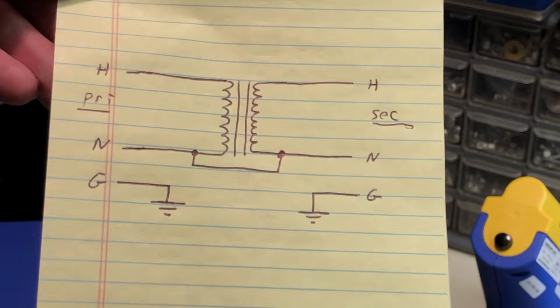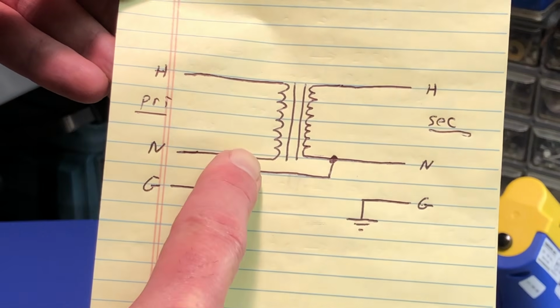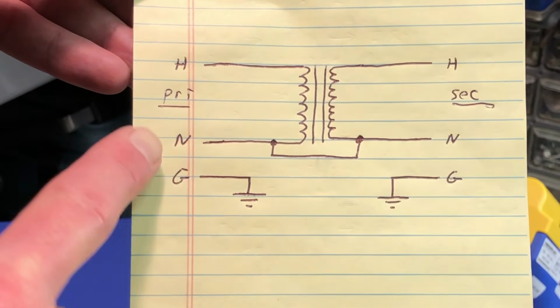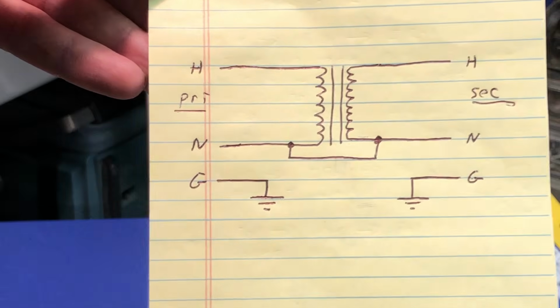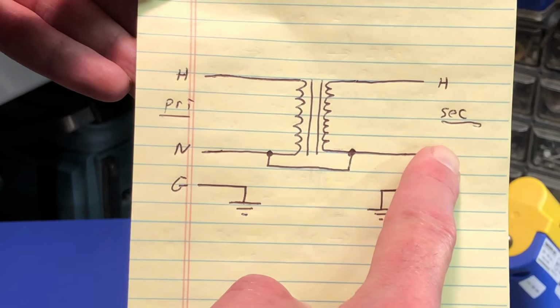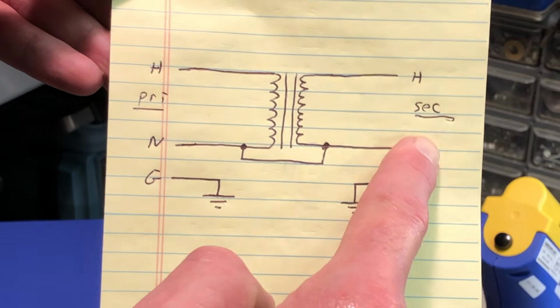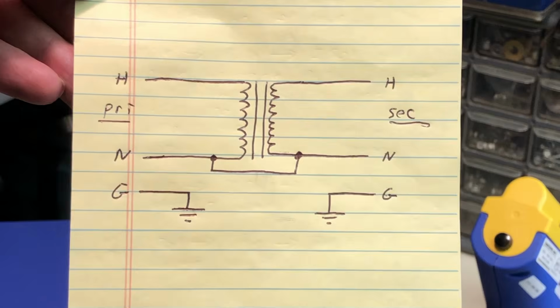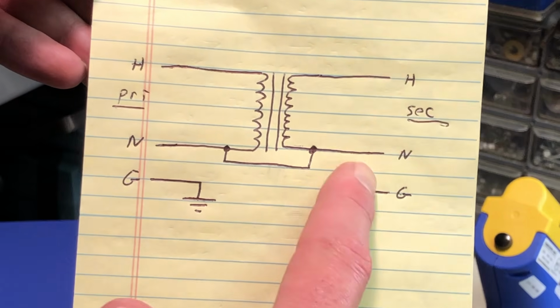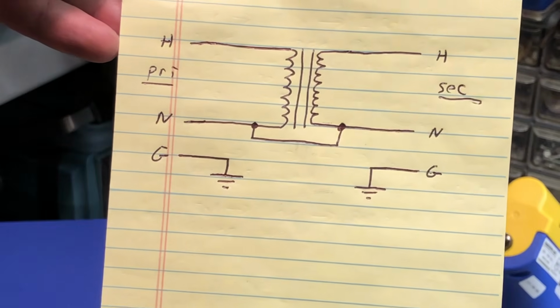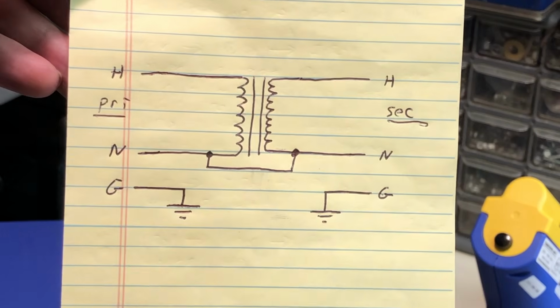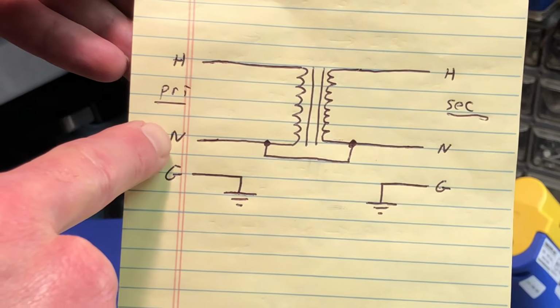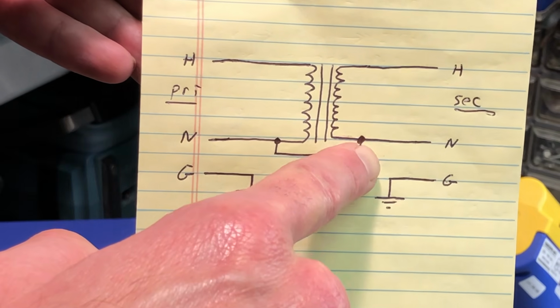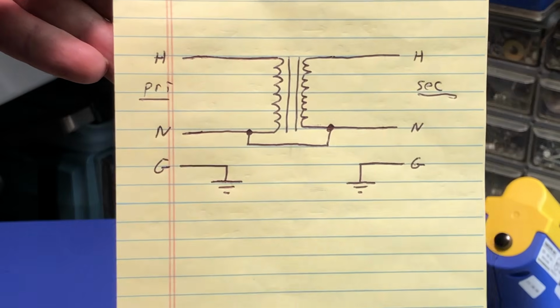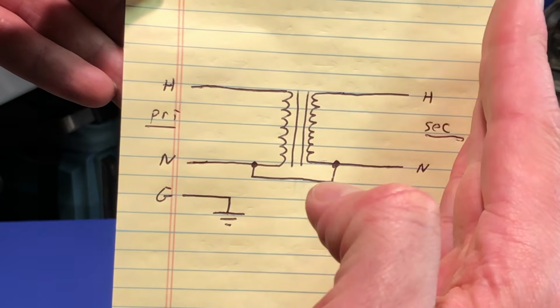And the reason that this does not work is because this neutral being connected back to the neutral that goes ultimately to your breaker panel, the neutral is connected to earth ground in your breaker panel. So you effectively have the neutral over here on the secondary going to the piece of equipment that you're working on, going to earth ground. Well, you're standing on earth ground when you're working, and so now a shock hazard exists between the hot. If your hand comes in contact with this hot, it goes through you, through your feet, through something that you're standing on, through earth ground to the breaker panel, and then comes back over here to the other side of the transformer. So that won't work.